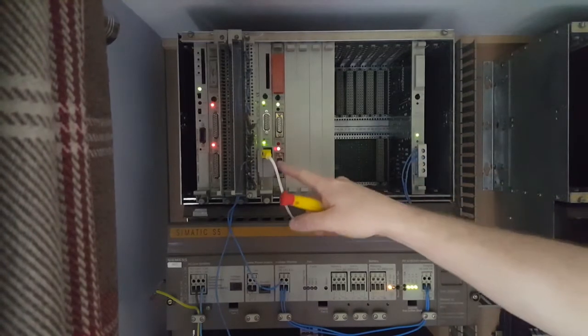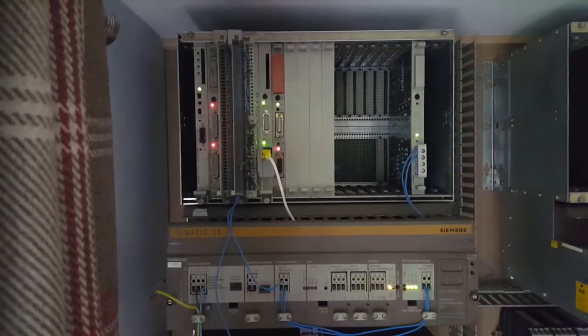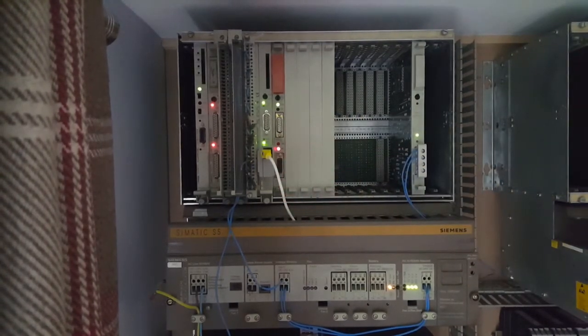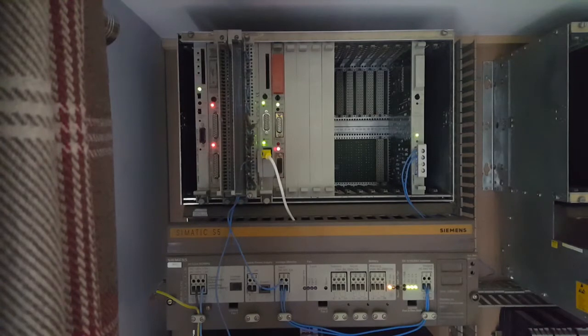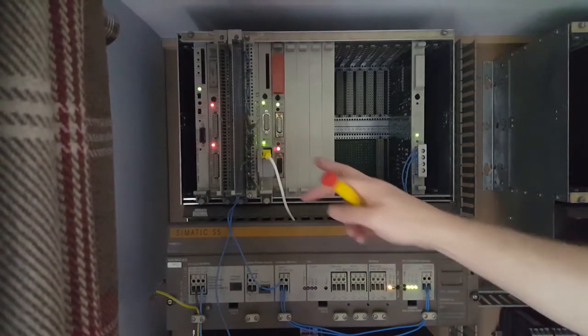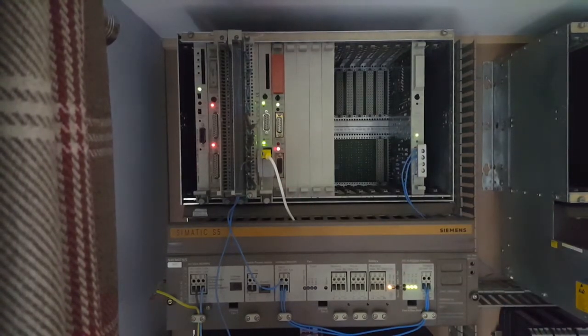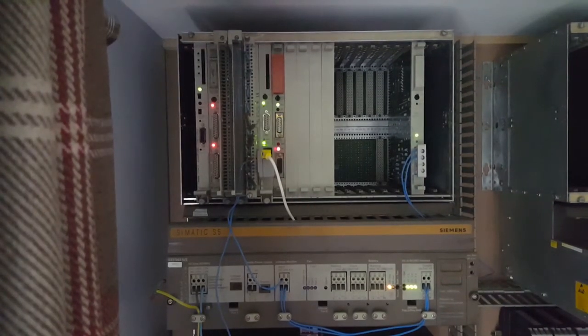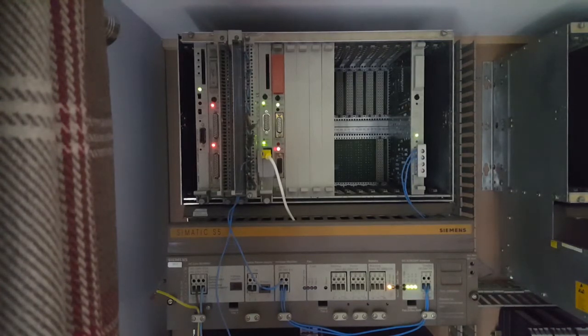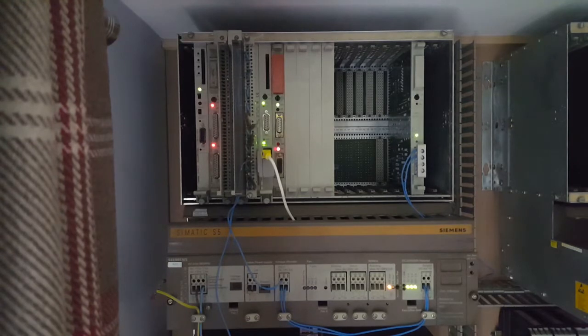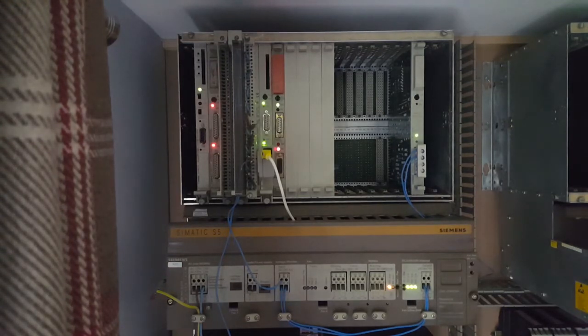This card here is an Ethernet card. I have plugged in an AUI to RJ45 converter so I can connect the PLC to my office network. The card is configured with an IP address of 192.168.1.100 and is configured to send and receive jobs on port number 1001.